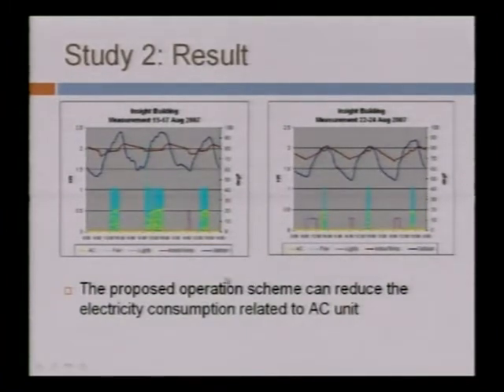In the previous study, we only measured the watt hour, the energy for the air conditioning unit. For this second study, we also put a current transformer on the fan unit inside the mechanical room, and on one of the lights. Looking at the energy consumption pattern, the yellow dots indicate that the air conditioning unit is on, operating at the same time as the fan, so we know it's connected.